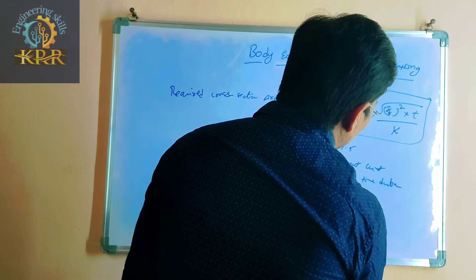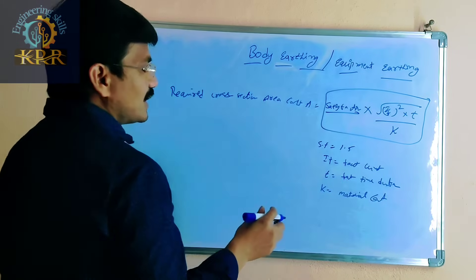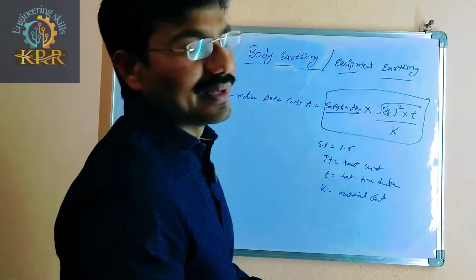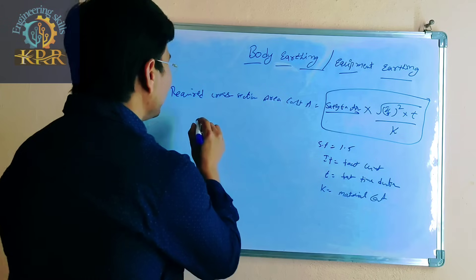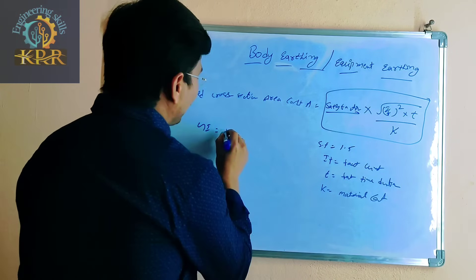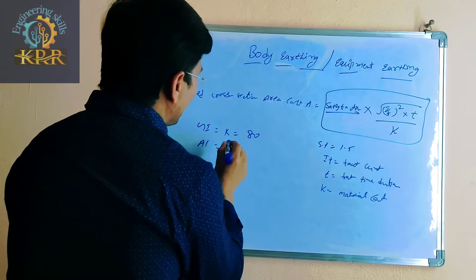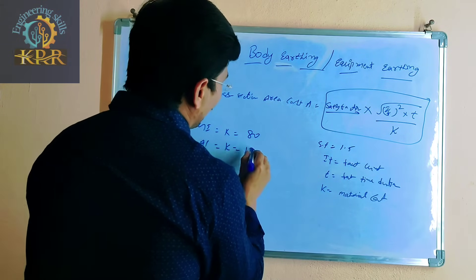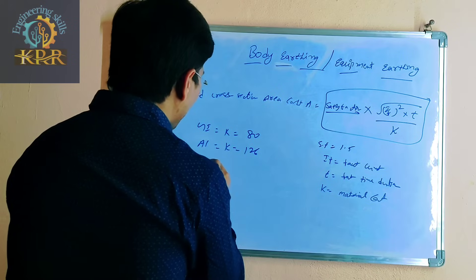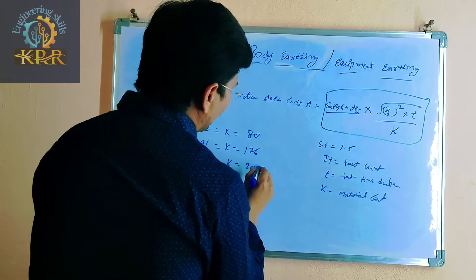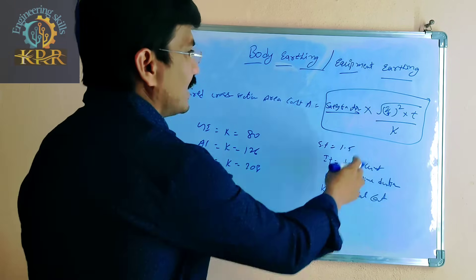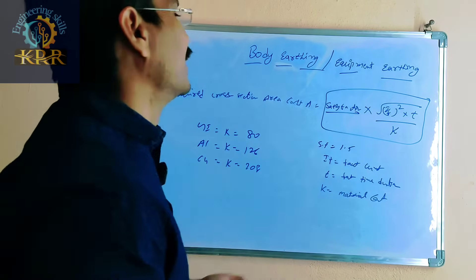K is called the material constant. The material constant is different for different materials. If you are using a GI strip, the material constant is 80. If you are using an aluminum strip, the material constant is 126. If you are using copper, the material constant is 208. Whichever material you are using, use the corresponding K value in the formula.